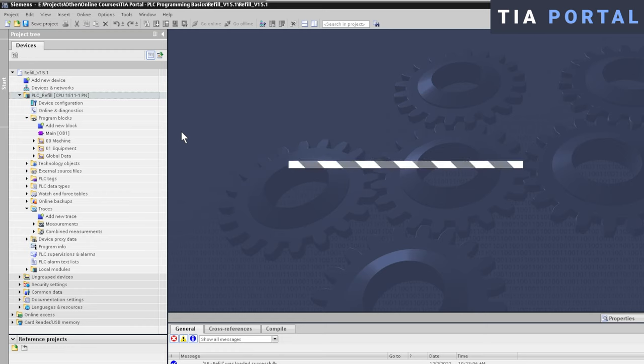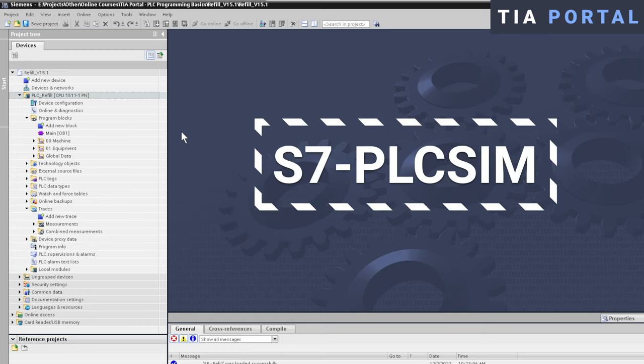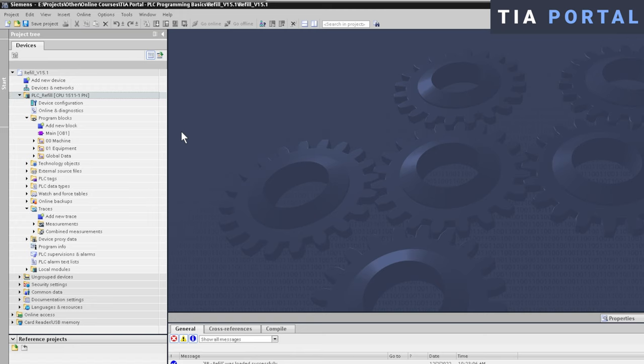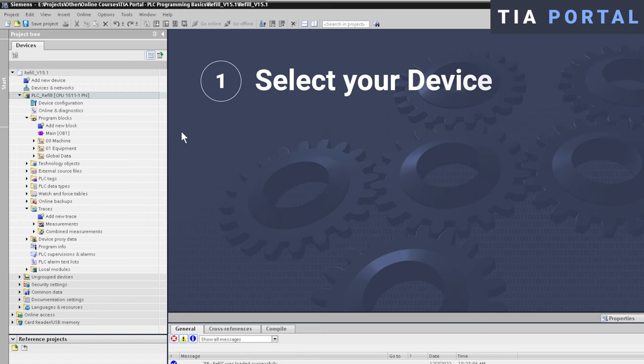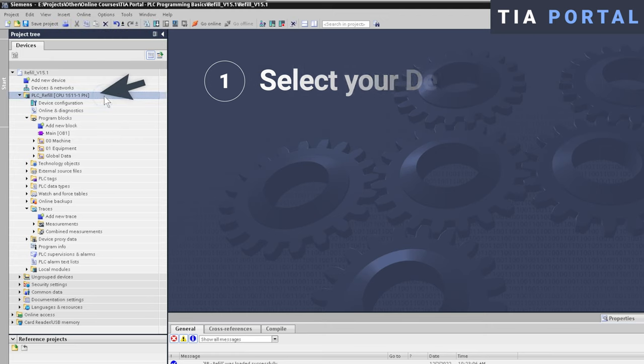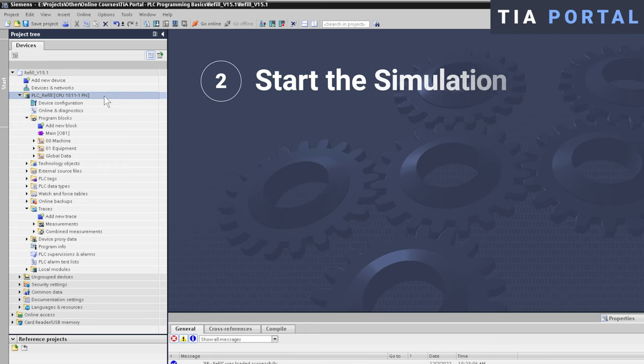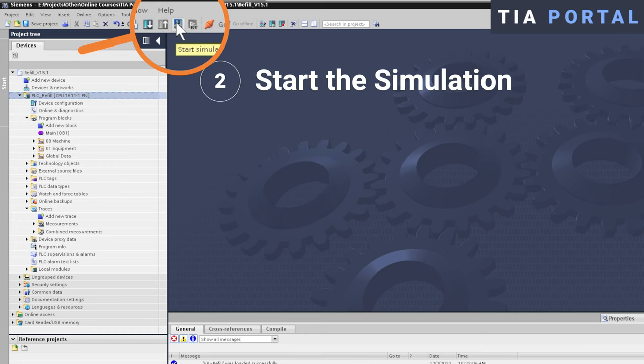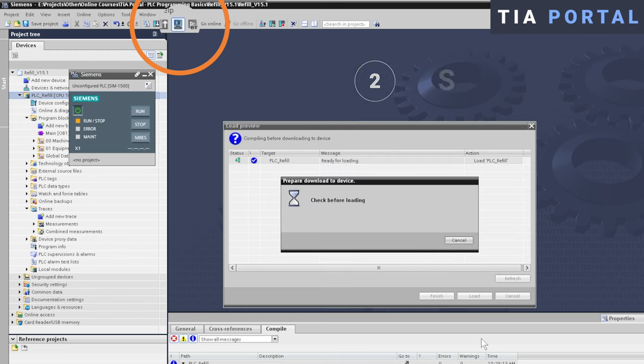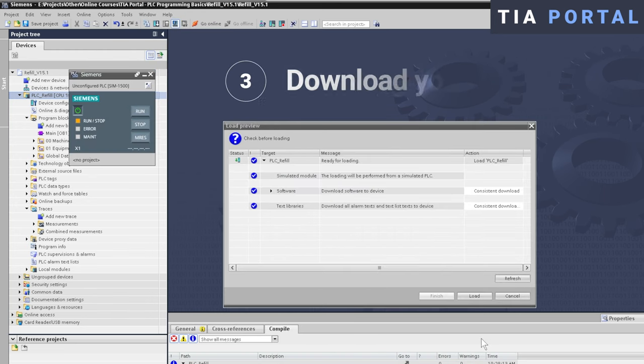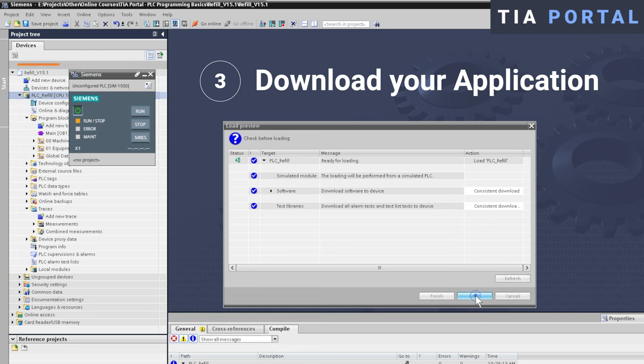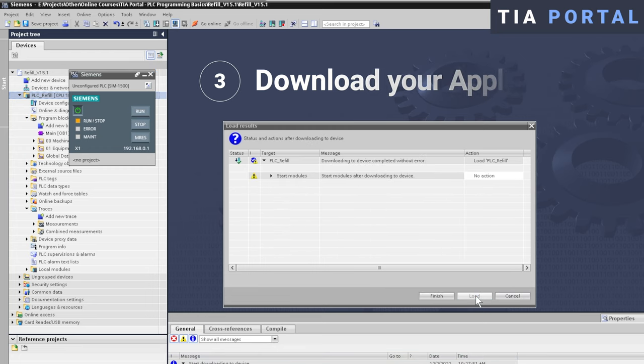Both platforms give you the option to simulate your PLC application using Siemens' own proprietary Step 7 PLCSIM software. But where TIA Portal really shines is that Step 7 PLCSIM is completely integrated in the TIA Portal automation platform. To simulate any application in TIA Portal, just follow these three easy steps. First, start by selecting the device which you want to simulate, like for example the PLC of our sample application. In a second step, you start the simulation by pressing the icon right here in the top bar. And in the third and final step, you download the application to the Step 7 PLCSIM simulator, which is opened here on the left side.